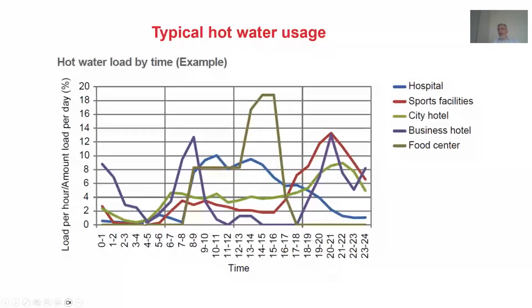If you see here, for a business hotel, you start in the morning, people wake up, start taking showers, baths, and everything. Your demand goes up, and let's say up to 9 o'clock you have a high demand. Then demand started going down, and you have a small demand between 12 and 3, and then no demand, and after 4 o'clock you have demand again. So your load is not constant, and you have a peak demand where hot water is required in high volume for a certain period of time.